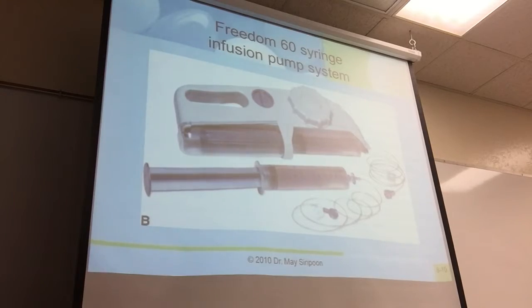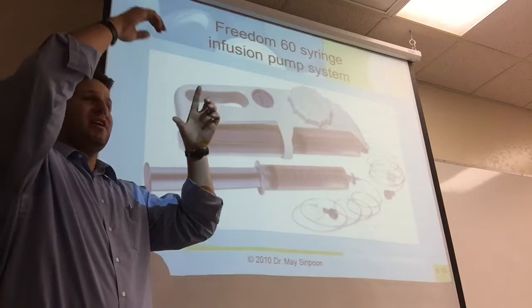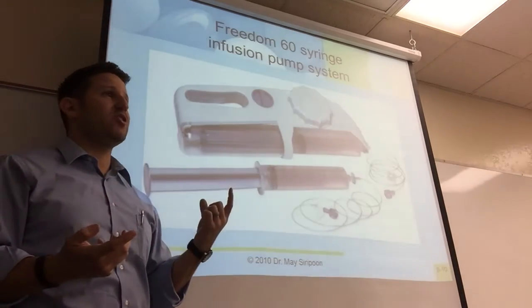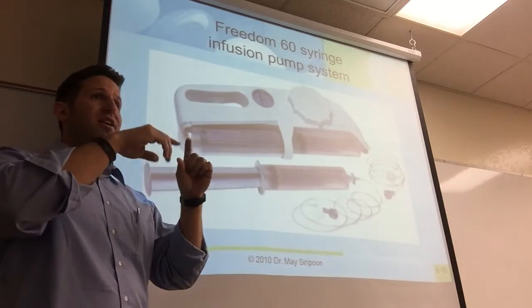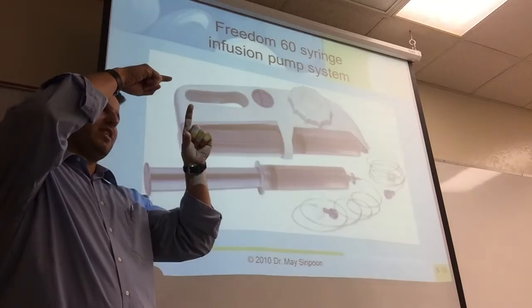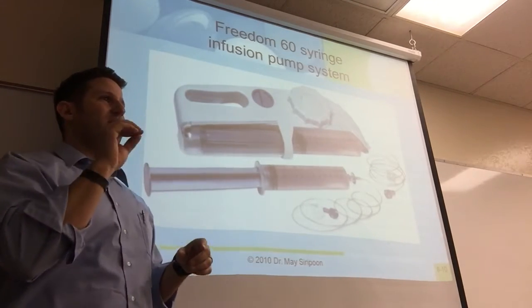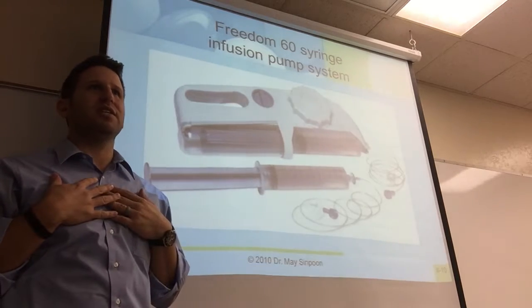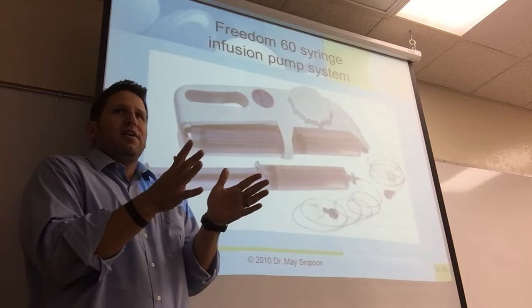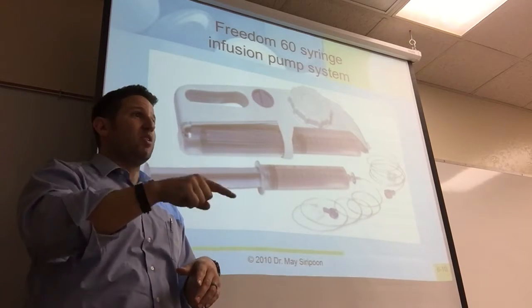Remember we talked about how on the big IV pump, the fingers go down and go blub, blub, blub, and they give those almost like miniature boluses. Well, for the pediatric patient, if they're on a drip, like a continuous medication flow, every time it goes down, it has to pause to go back up. For us, it's no big deal because we have a lot of volume to absorb, but for the tiny neonate, that one run down to the fingers is a bolus of the medication.